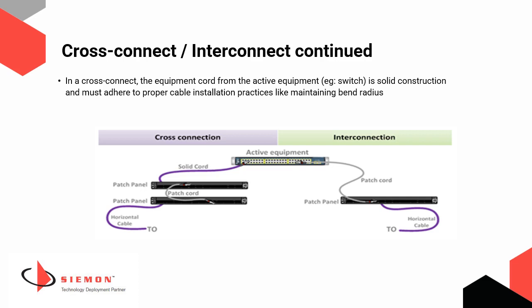The benefit of this design is that the expensive active equipment can be mounted in a separate secure cabinet away from the passive patch zone, thus preventing any tampering with the active equipment. The drawbacks are that this design requires more rack space, more cabling components, and more labor required for the installation, all of which adds up to higher costs.